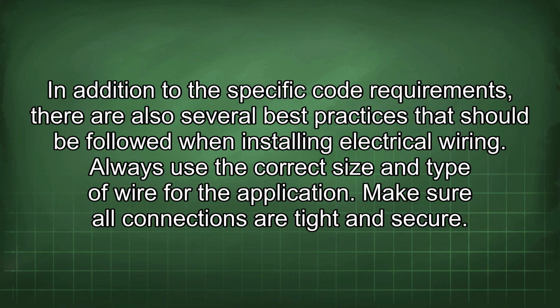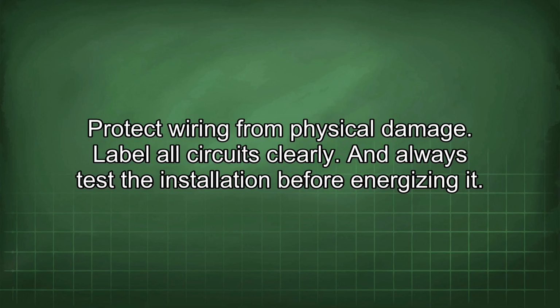In addition to the specific code requirements, there are also several best practices that should be followed when installing electrical wiring. Always use the correct size and type of wire for the application. Make sure all connections are tight and secure. Protect wiring from physical damage. Label all circuits clearly. And always test the installation before energizing it.